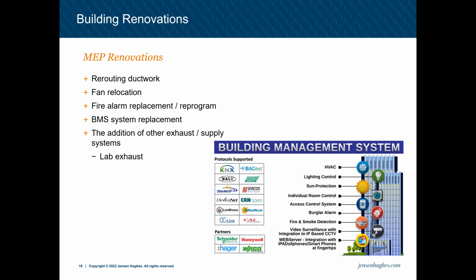Sometimes the smoke control system can be monitored by the building management system, the BMS. And we've worked on multiple projects where the BMS was replaced or upgraded, and programming within the BMS that was specific towards our stair pressurization, mechanical items had changed and changed the parameters of which our fans were running. One specific one, we were working in a building out in Cambridge. The BMS had our VFD running at 75% of what it was supposed to be.